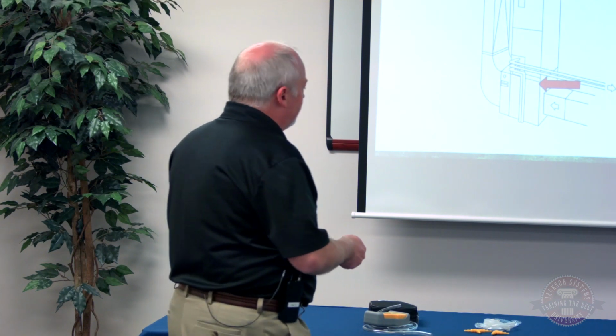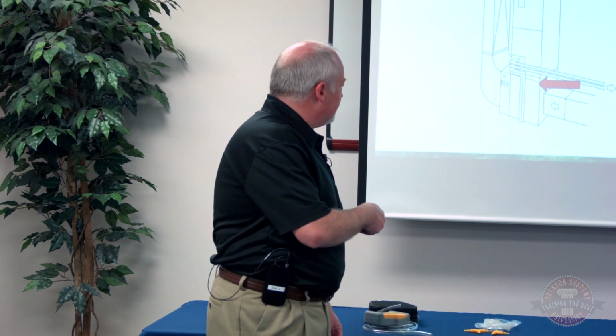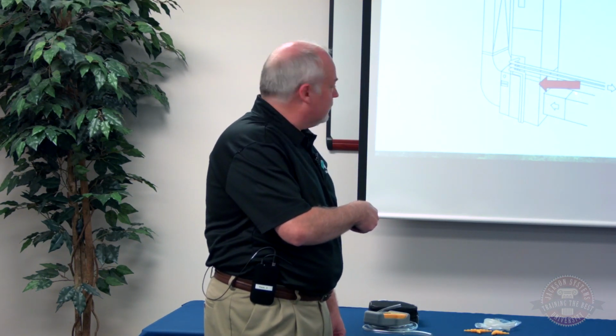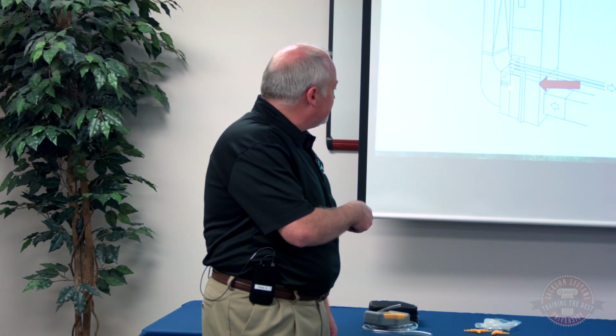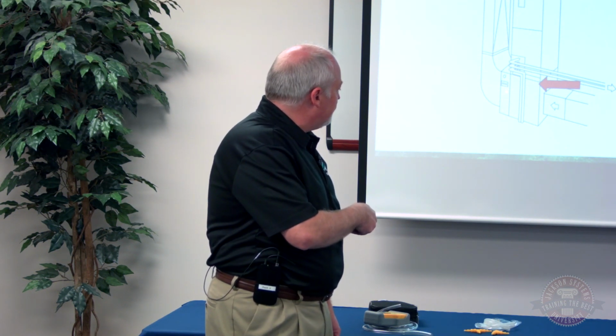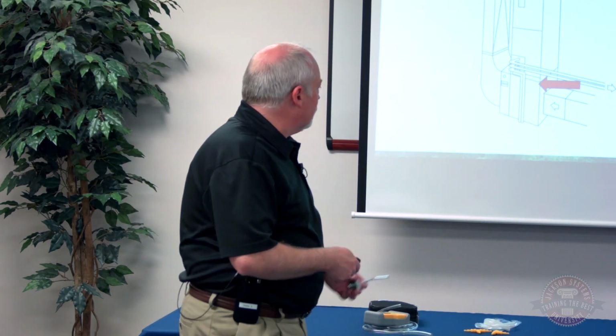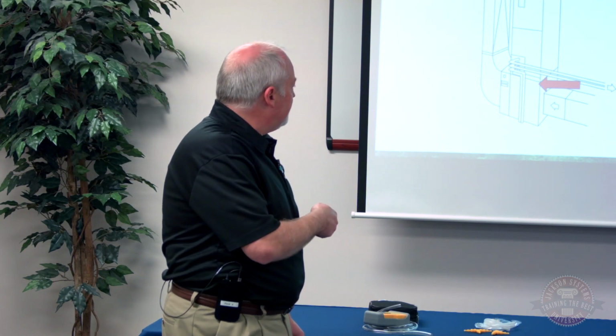So we're going to put one of our static pressure tips here at the return, at the inlet of the air handler. If we've got a filter on the system here, we want to put it in between the filter and the air handler, because we don't want that filter to be part of our equation when we're looking with these tips. The other tip is going to go at the outlet of our air handler. So now we're measuring what that equipment is seeing as it was shipped and tested at the manufacturer.